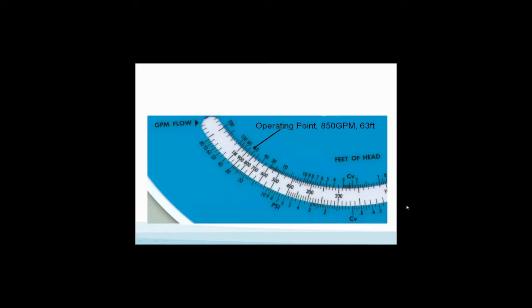And what are we after? We would kind of like to know what head we need at 650. That's design flow, right? We're pumping 850. We kind of like to know what it would be at 650. Now, you know what we're really after is to meet the design need at 650 GPM. So all we got to do once you plug that in, you set that up, and we just go to 650, for example, on this particular screen, and you'll see we need about, what, help me out here, about 36, 37 feet of head to do 650 GPM.